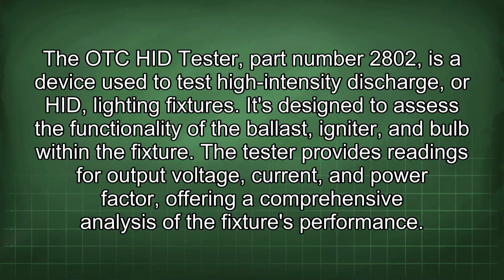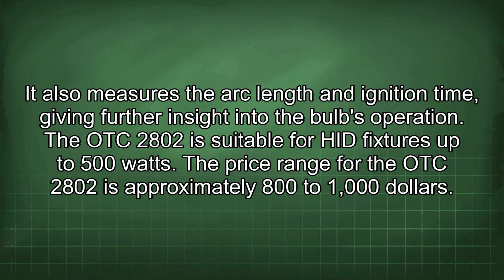The OTC HID tester, part number 2802, is a device used to test high-intensity discharge, or HID, lighting fixtures. It's designed to assess the functionality of the ballast, igniter, and bulb within the fixture. The tester provides readings for output voltage, current, and power factor, offering a comprehensive analysis of the fixture's performance. It also measures the arc length and ignition time, giving further insight into the bulb's operation.